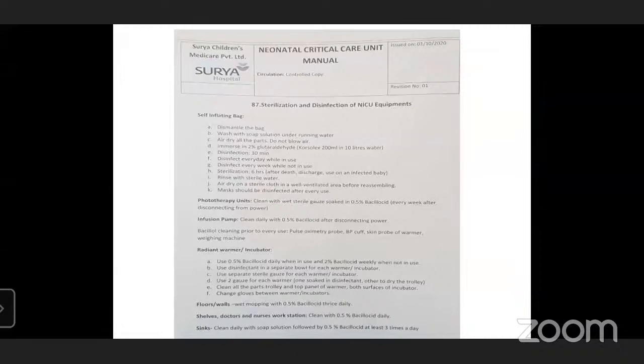Why is it required? Because if you have water content in that and you put it into your disinfectant, your 2% glutaraldehyde will become 1.5% or 1.25% glutaraldehyde, which is no longer a disinfectant at all. Your 2% glutaraldehyde works only as long as it is 2%. So it is very important that all your equipment is dry before it's put in the drum - it has to be washed and dried before you put it into the drum.